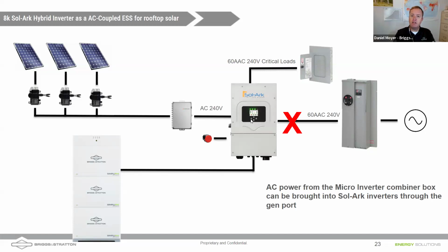So the concept here is when the grid goes down inside of the solar, within milliseconds, the solar is going to disconnect from the grid, using energy stored in the batteries. It's going to form a grid that the microinverters recognize and continue to operate. When the batteries start to get full, the solar will start to use frequency shifting to raise the frequency of the sine wave to curtail the AC microinverter's output so we don't overcharge the batteries. And we call that frequency shifting.